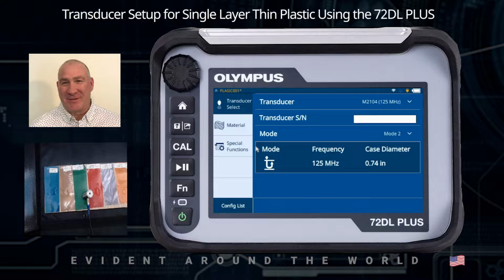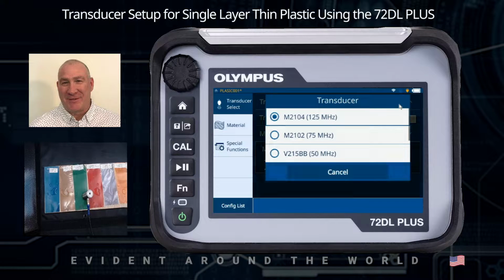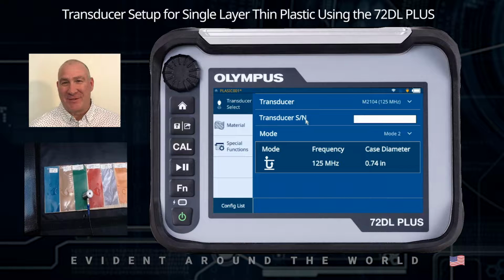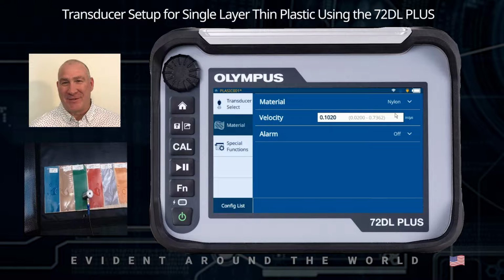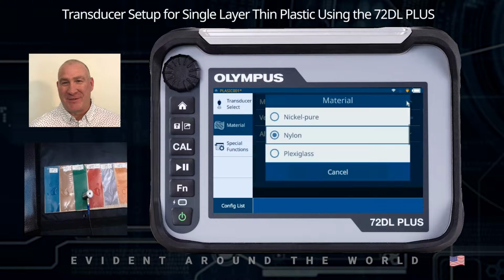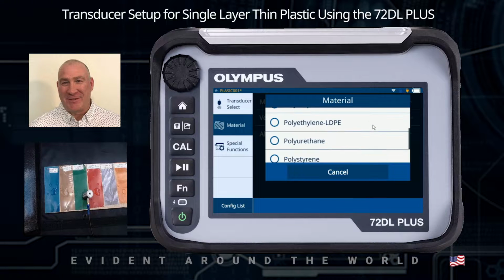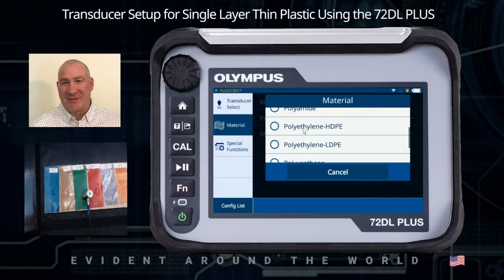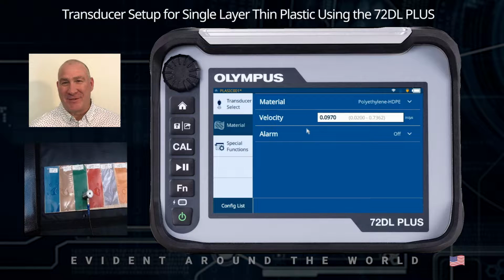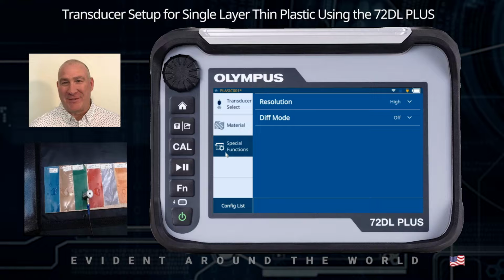This brings me up to the configuration list. The first thing I want to do is select the transducer to make sure it matches what I'm using. In this case here, I want to use the M2104. I could enter a serial number if I wanted to. I also have to select the mode of measurement. We're going to be doing a mode 2 measurement. Make sure that's selected. Next, you can touch on the material tab and we can select the material so we can get a good ballpark velocity. So this is a plastic material. So what I'm going to do is select one of the plastic settings for polyethylene, high density. And the last thing I want to do is check the resolution. I want that set to high, which it is.